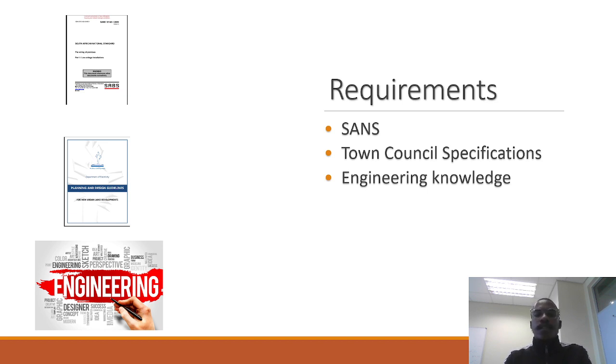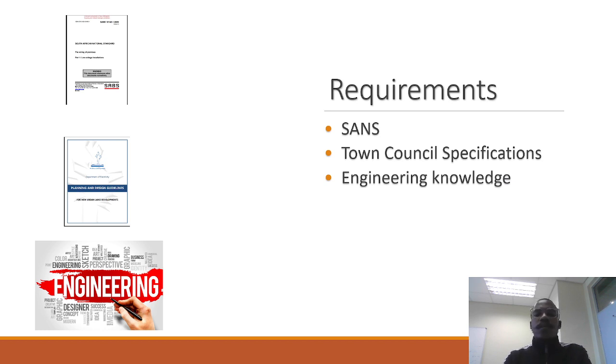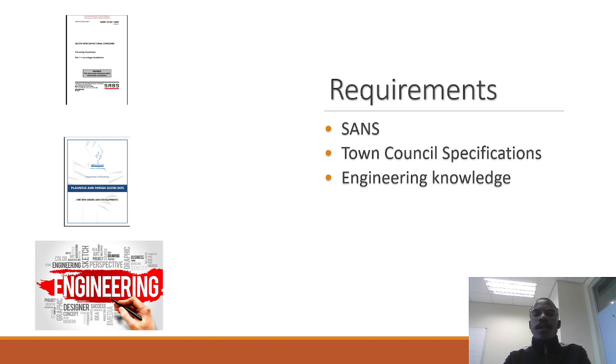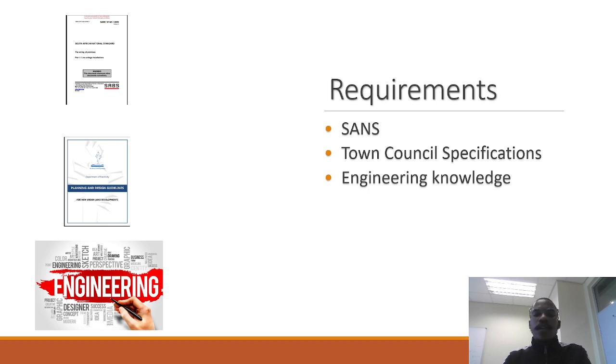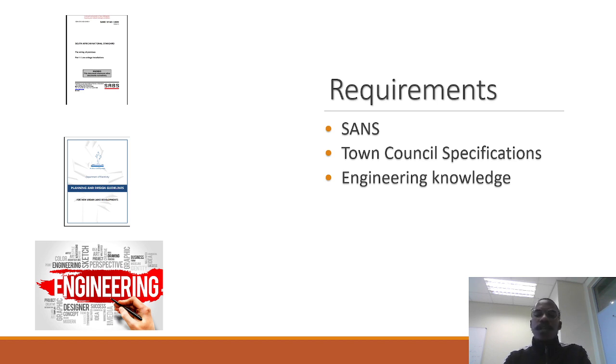For example, Windhoek and Swakopmund will have different specifications. In Windhoek, if you have to set up a miniature sub, you can just set it up in an open area. But in the Erongo region or specifically Swakopmund, due to the dew and the Benguela current and the effect of rust, you would require to set up a separate building to prevent the cables from being damaged from the rust and other harmful weather conditions.